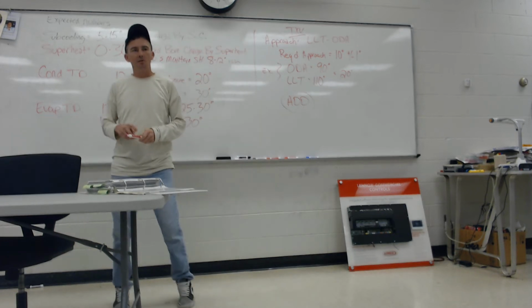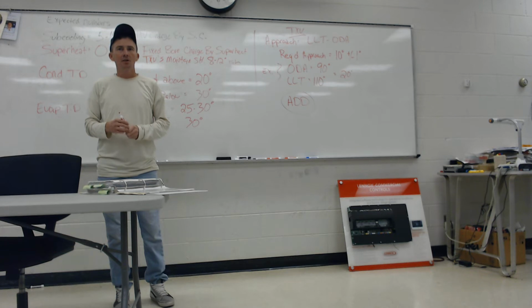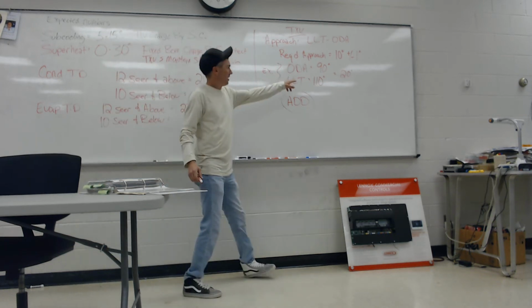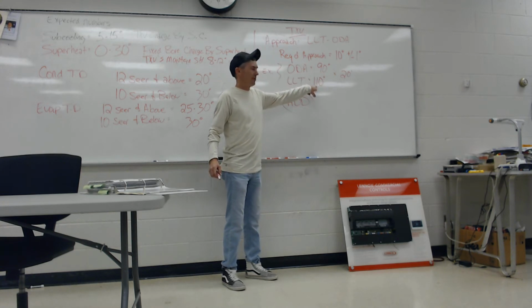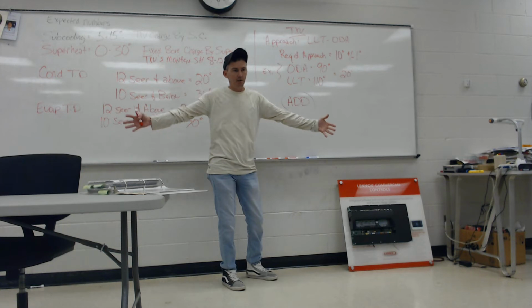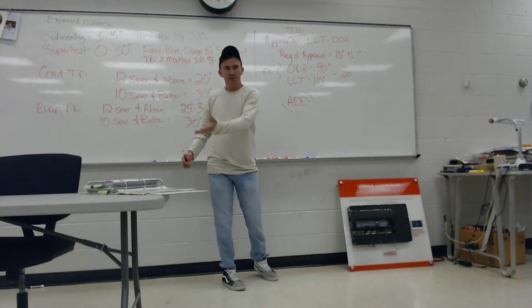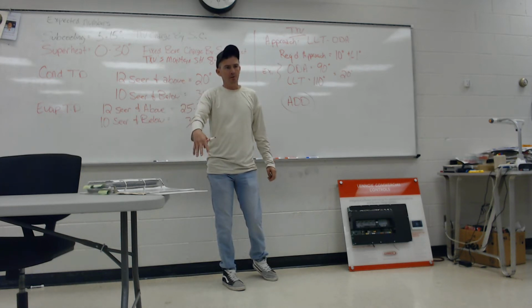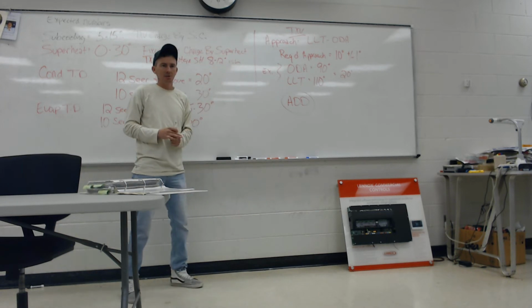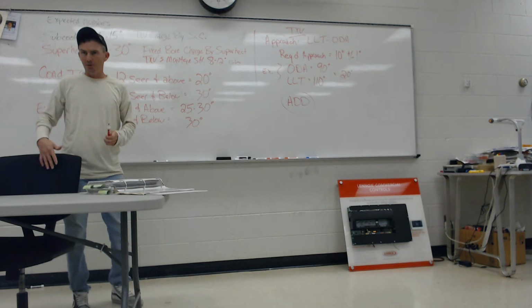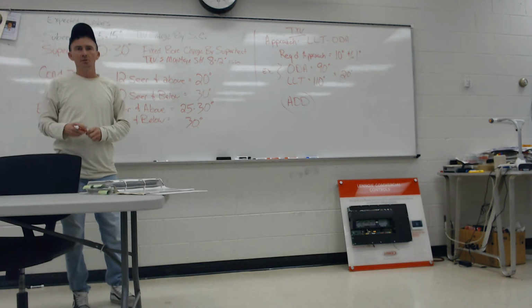The longer it stays in the condenser, the closer we can get it to ambient air. In a perfect world, if it's 90 degrees outside, I'd love to get my liquid line all the way down to 90. Use 90-degree ambient air, blow it across the condenser, drop the refrigerant temperature all the way down to 90, that'd be awesome. But condensers aren't 100% efficient. There's always some loss there. You could stack a huge condenser, you could totally do that.